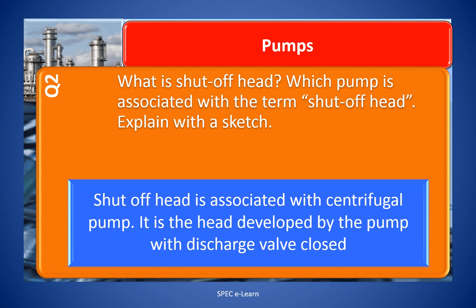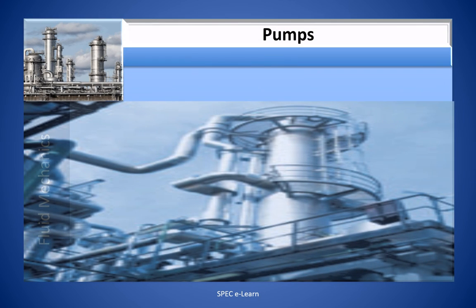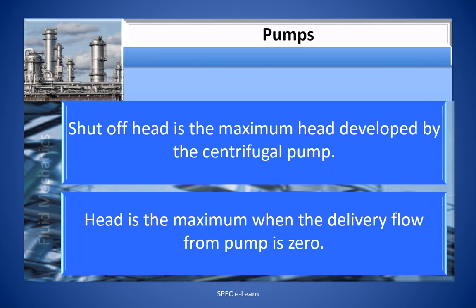Shut-off head is associated with the centrifugal pump. It is the head developed by the pump with the discharge valve closed. Shut-off head is the maximum head developed by the centrifugal pump. The head is maximum when the delivery flow from the pump is zero.